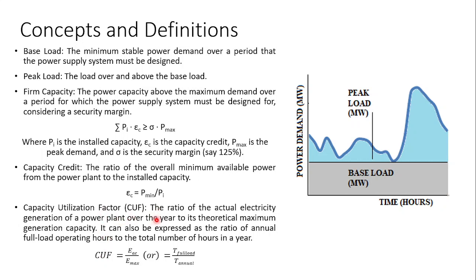So this is capacity utilization factor. You have a plant, let's say designed for 1 megawatt. In one day, that plant should produce 24 megawatt hours, because there are 24 hours in a day: 1 megawatt multiplied by 24 hours is 24 megawatt hours. It must produce that much, but solar cannot produce that much. For instance, it can produce only in the morning or afternoon, so it can produce at most like 4 or 5 megawatt hours. That is, it will operate at full load for only 5 hours, let's say. So your capacity utilization factor is 5 megawatt hour, which the plant has produced, divided by your theoretical maximum, which is 24 megawatt hour.